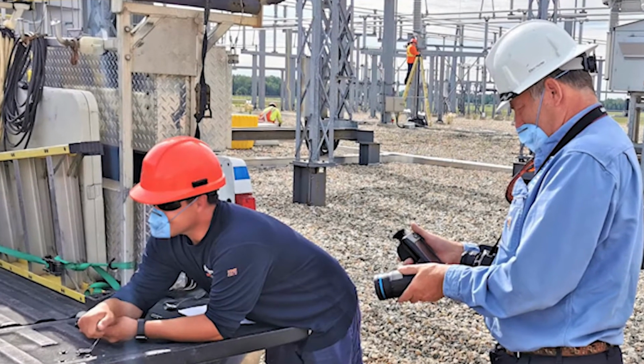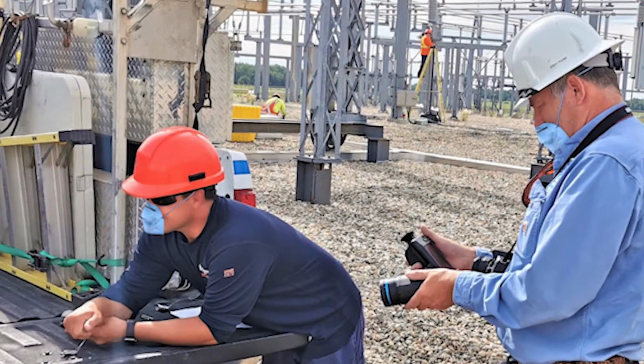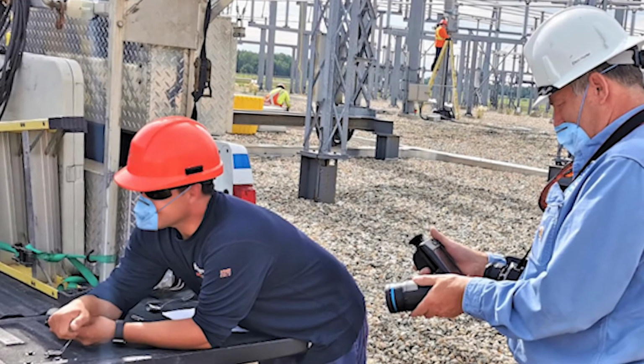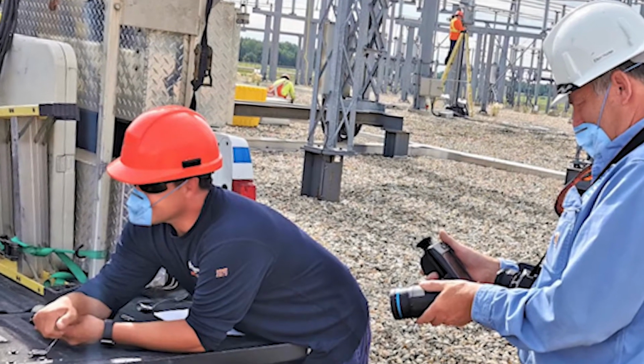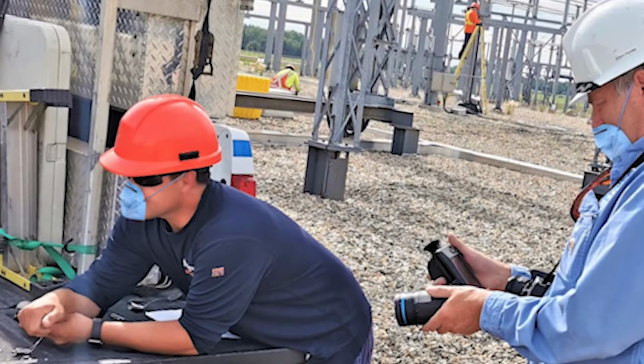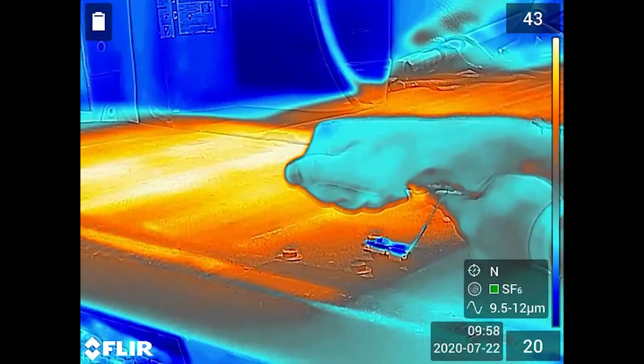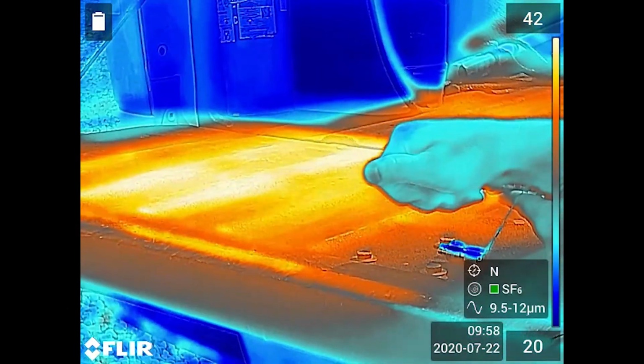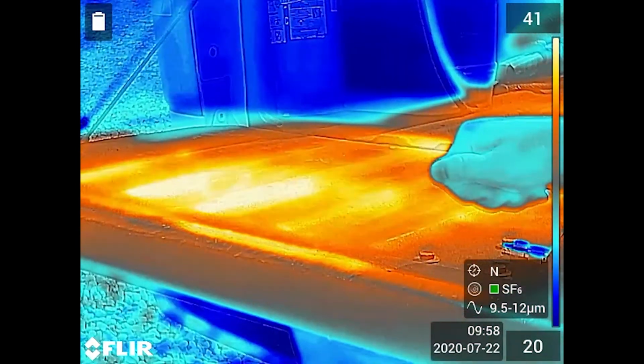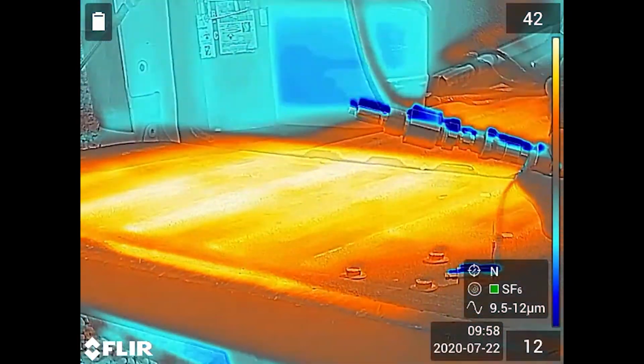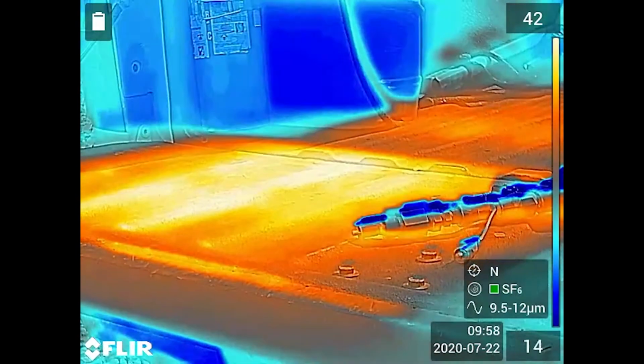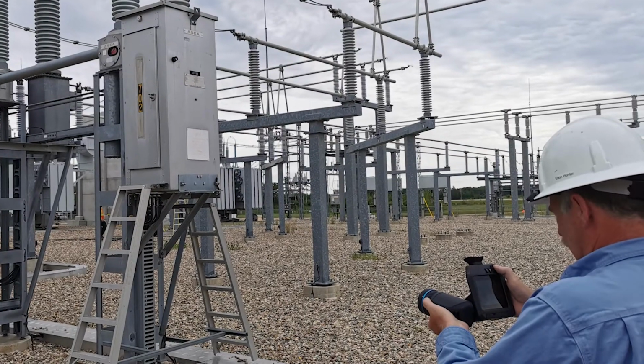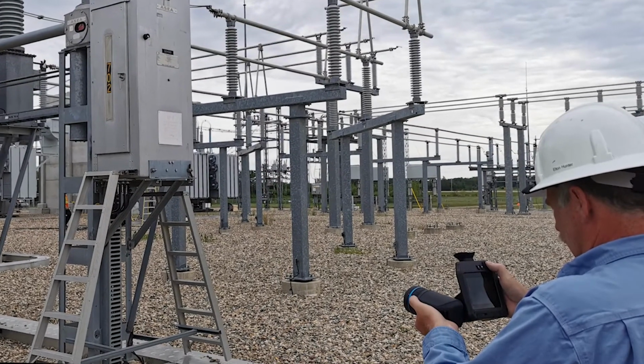We had the station operator help us to facilitate the bump test. He is holding the SF6 canister on the tailgate in preparation to release the small amount of gas, and Elton Hunter is operating the camera. You can see as we do the test that the gas is very visible. You can see the SF6 gas escaping, and this is a good way to confirm that everything is set correctly and operating properly. This is the first time that we've had an opportunity to work with this particular camera.